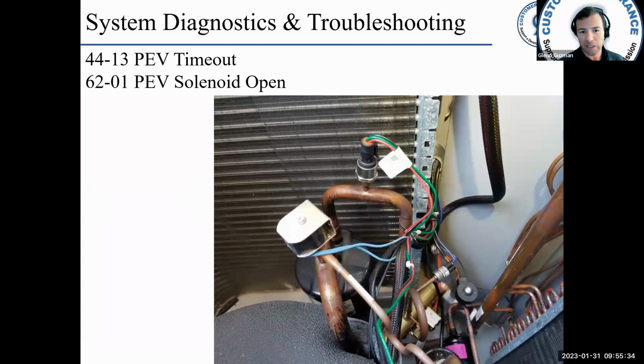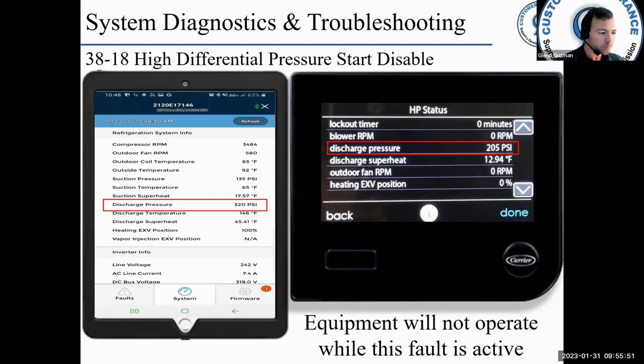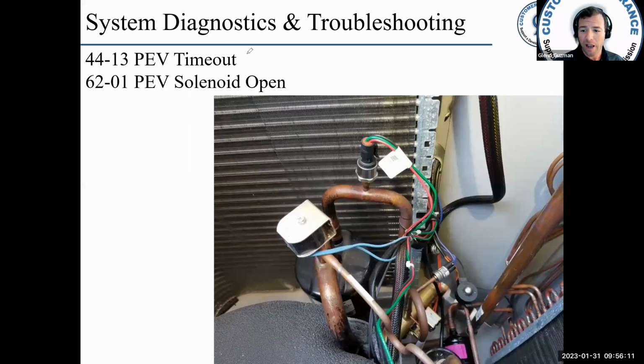Okay. You may also see a 4413 PEV timeout or 6201. It's kind of unrelated, but the PEV timeout you will usually see with your high pressure differential start disable. At least a couple of times I ran into this code, we had an issue with the transducer. The transducer was reading incorrectly and the system saw a high differential and would not allow it to start. Like I said, the PEV will open and try to reduce the pressure differential. After 10 minutes, you're going to get the PEV timeout if the pressure differential has not been reduced.